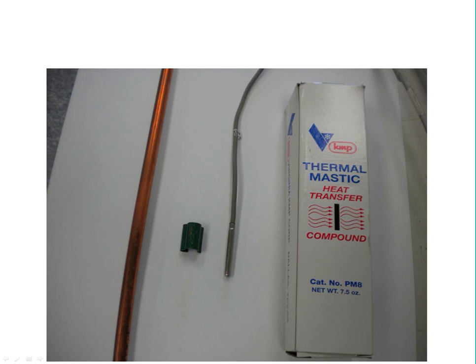You want to make sure that you're applying that to the thermistor and the area that you're attaching the thermistor with or on, so that you're making sure that that product helps you transfer the temperature so that that thermistor can soak out, giving you the proper amount of ohms resistance representative to the temperature.